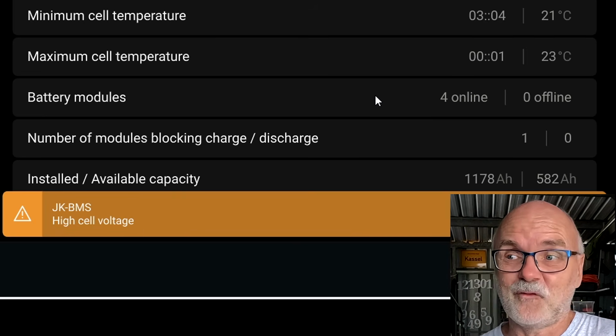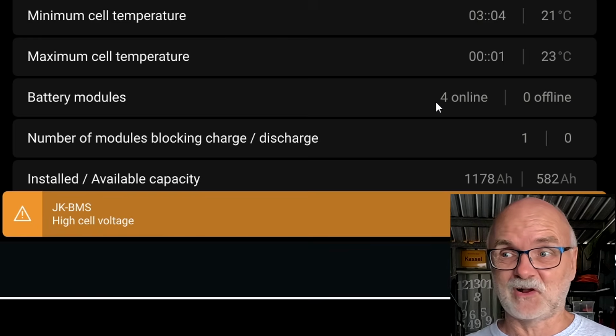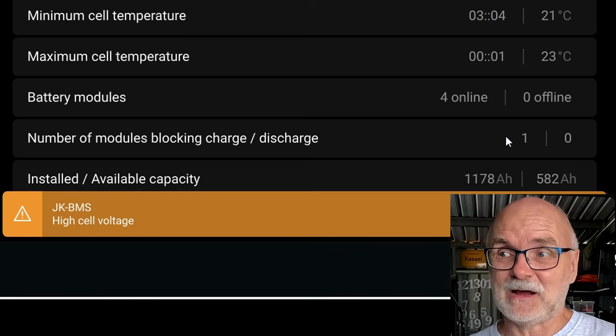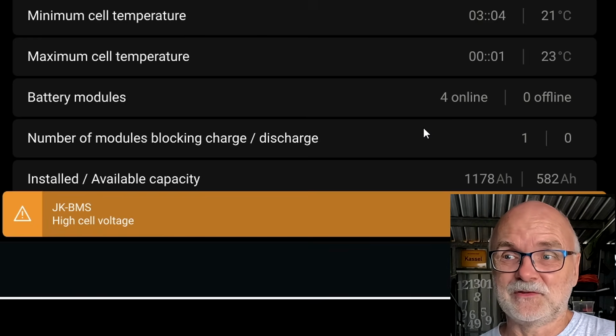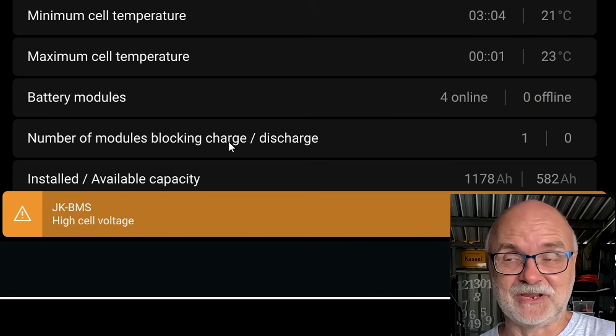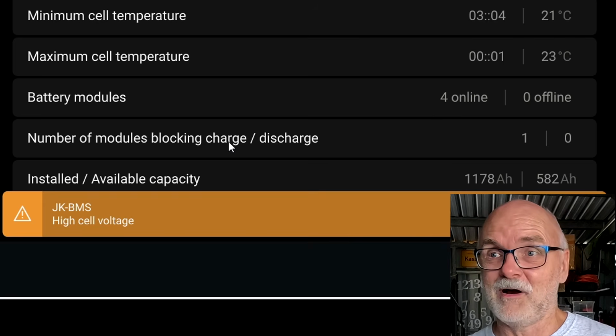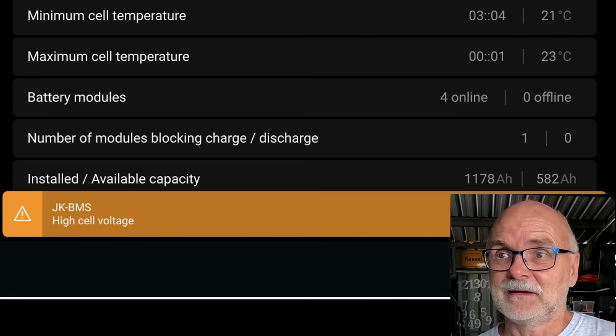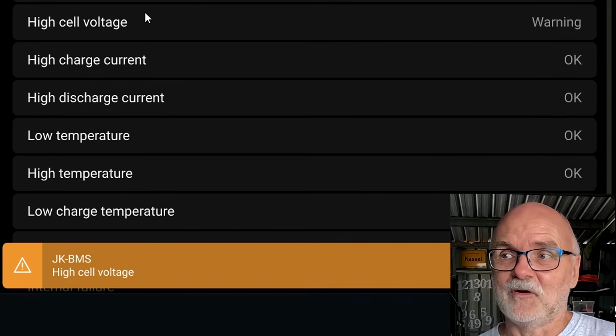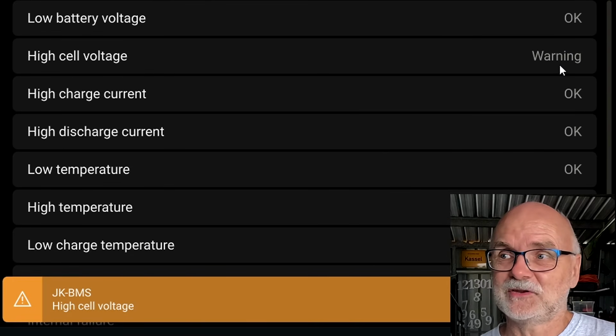Yeah, we still have 4 modules online. The BMS is still responding and everything, but you can see now here one of the modules is actually blocking charging. Yeah, this is our battery number 4, slave number 3. And let's have a look what's going on here in alarms. We have a warning here, high cell voltage warning.